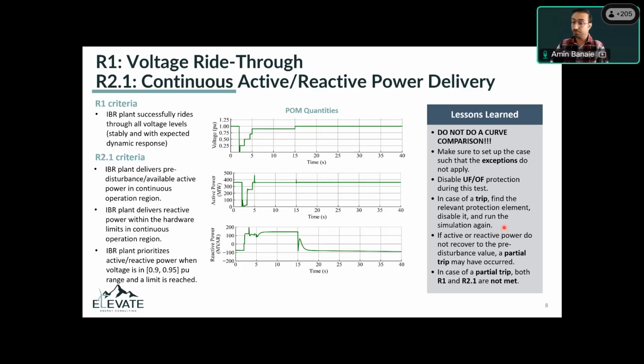Another thing, which is very important, is that if you see the IBR tripping, you go and find the relevant protection element that caused the trip, okay? And then don't stop there. What you need to do is to disable that element and then run your simulation again. And the reason for this is that if you just stop there, you're going to just see the first layer of the issue. There might be another under voltage element that wanted to trip but did not have enough time. And once you disable that first element, you're going to see that second element is going to again trip the plant. So I've seen cases where we have done this like 3 times and we have found like 3 faulty elements. So this is very important to do.